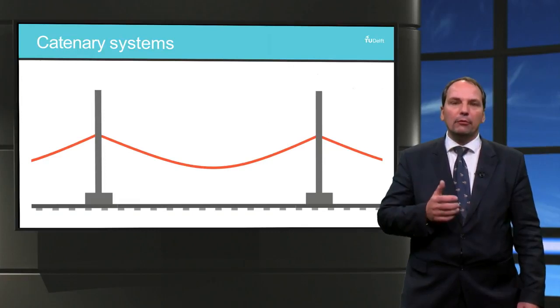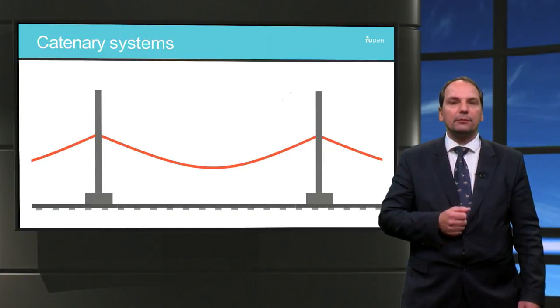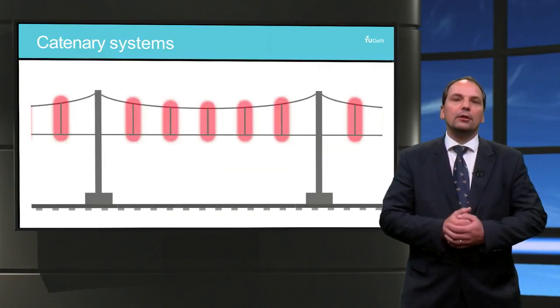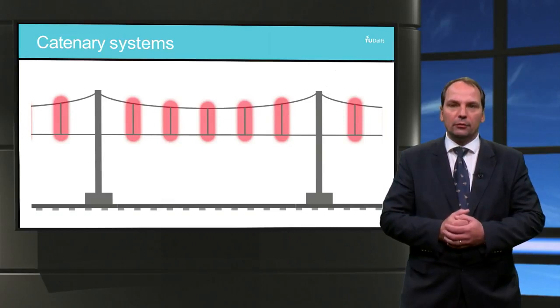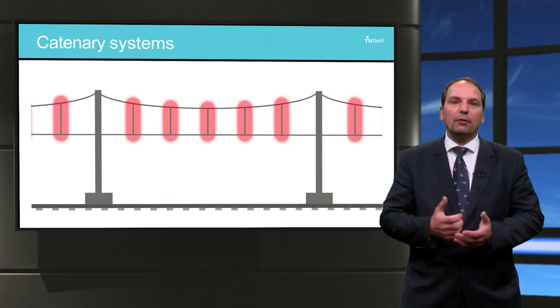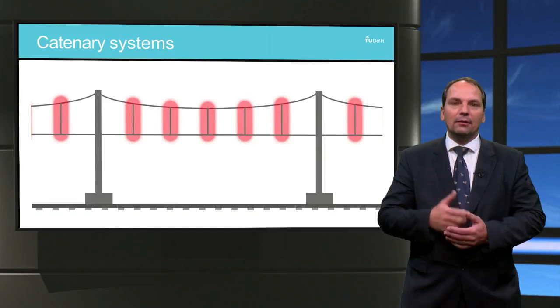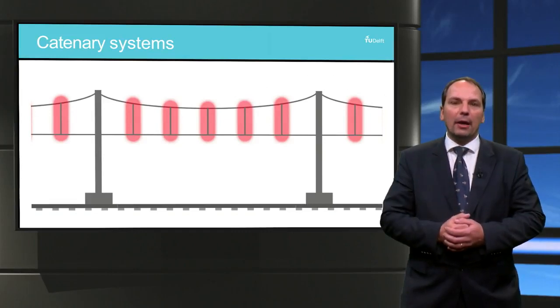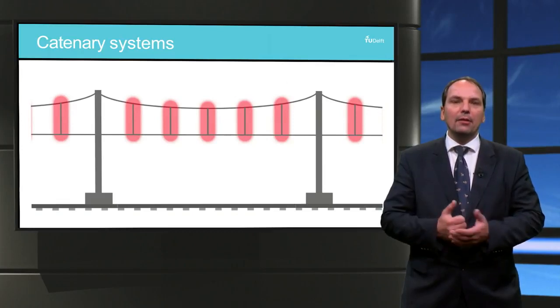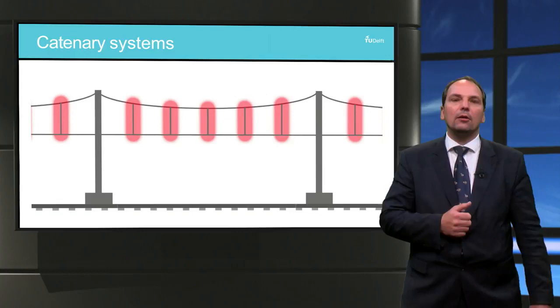It should also be rigid enough to interact dynamically with the pantograph. The solution is to use droppers at specific intervals. These droppers have variable length. The length is calculated based on different parameters, such as the tensioning loads of both the contact and messenger wire and their mechanical characteristics.